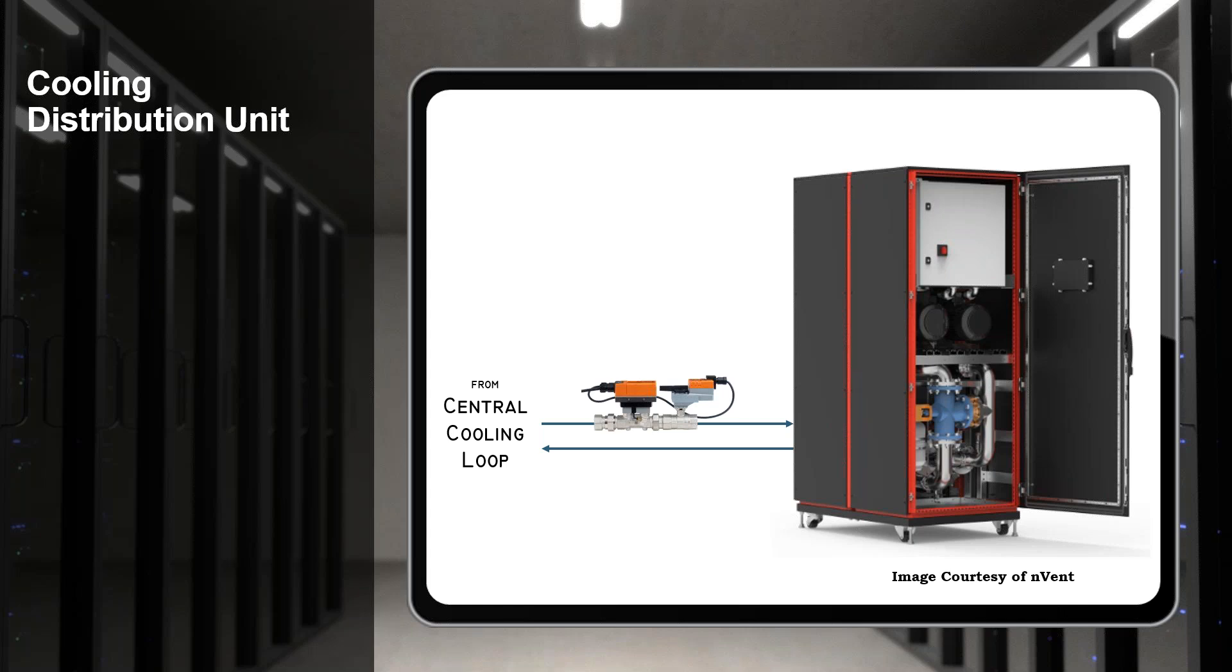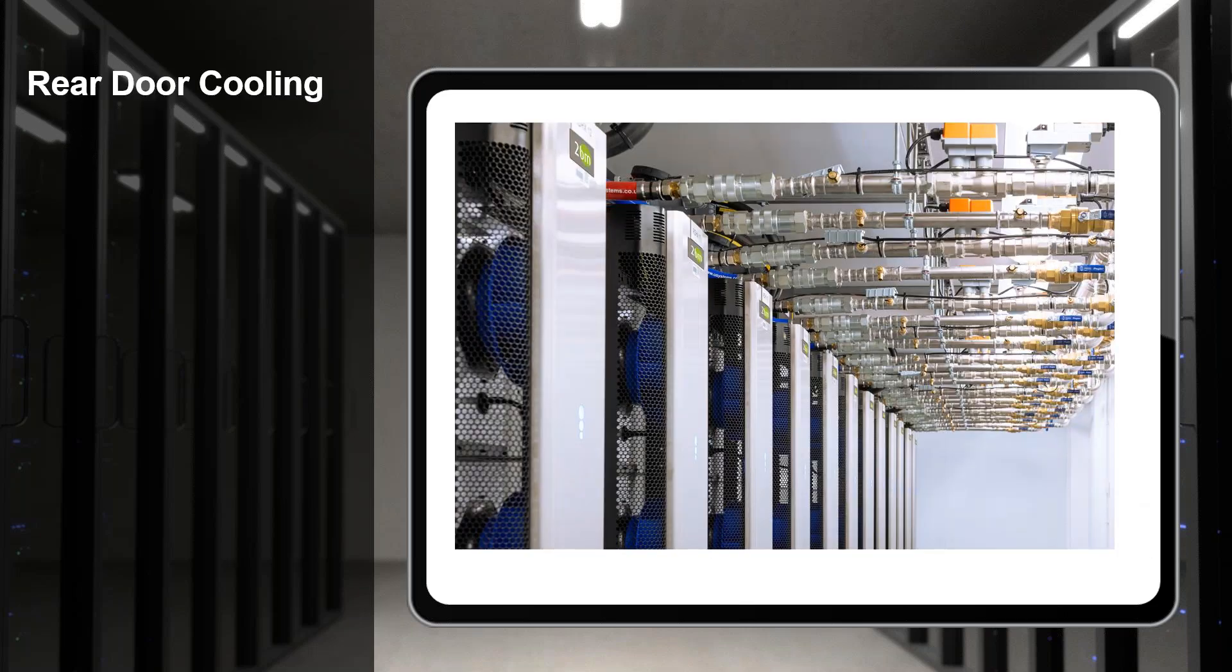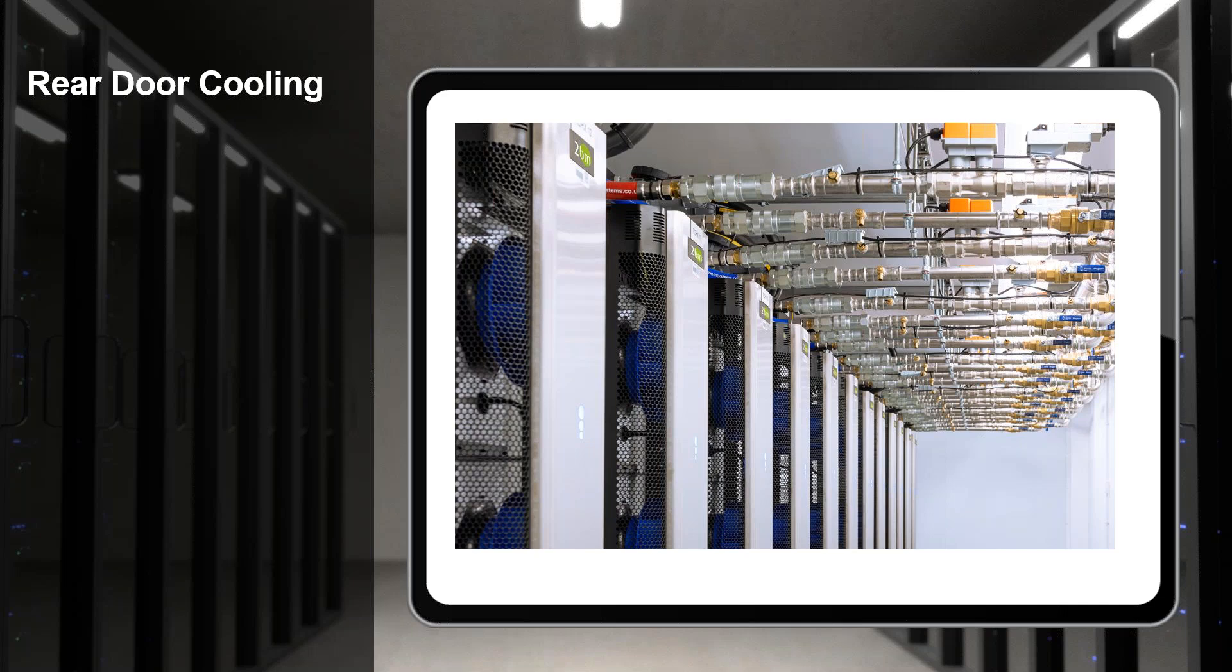Where does all the fluid from these CDUs go? They're going to go out into the technology space and address other types of equipment. Let's start with the rear door heat exchanger. The rear door heat exchanger just has a coil that runs through a set in the back of the rack. Some of them are active, meaning they have fans that blow the air through the servers. Some are passive so the natural airflow of the building pulls it through. But we're going to need fluid control to each of these. Here you can see a whole array of Belimo EPIVs controlling rear door heat exchangers.